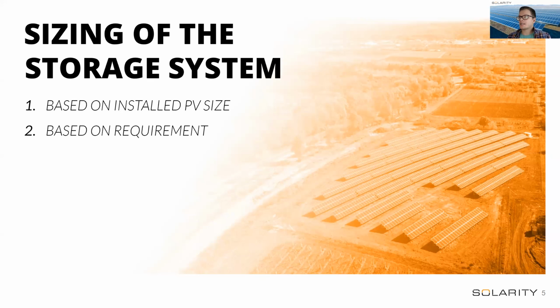A lot of people ask how to design and size the storage solution. Based on my experience, you need to take into account two criteria. First, the total installed capacity of the PV system on your roof or ground. For example, if you have 10 kilowatts of installed PV solar system, the most ideal, perfect capacity of the solar storage system is also 10 kilowatts. So the ratio is 1 to 1.